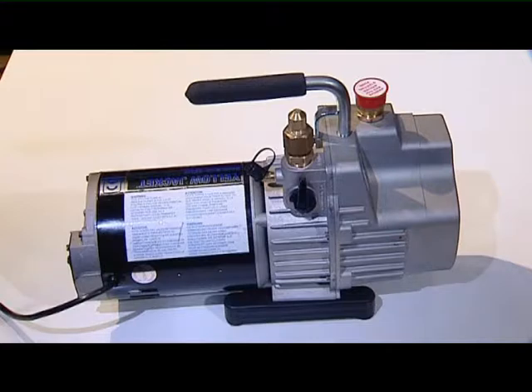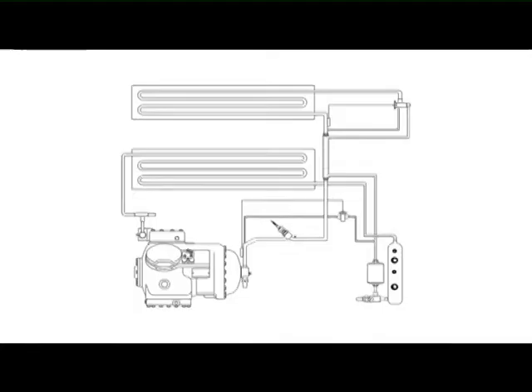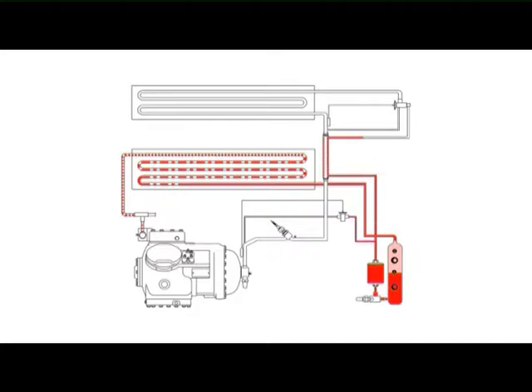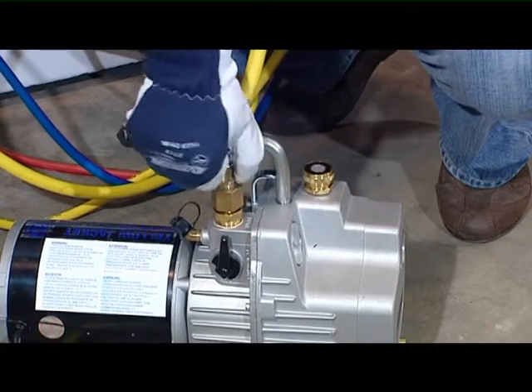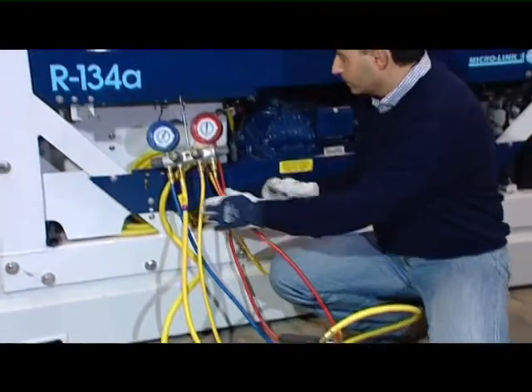The vacuum pump. Moisture is the deadly enemy of the refrigeration system. The presence of moisture in a refrigeration system can have many undesirable effects, the most common of which is the formation of acids, resulting in metal corrosion. For this reason, it's very important that a refrigeration system is properly evacuated and dehydrated before filling the refrigerant. The essential tools are a vacuum pump and a gauge manifold set.